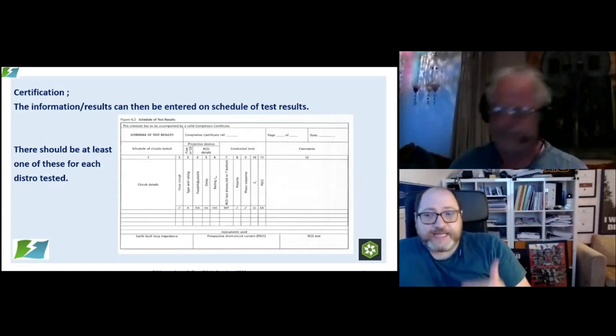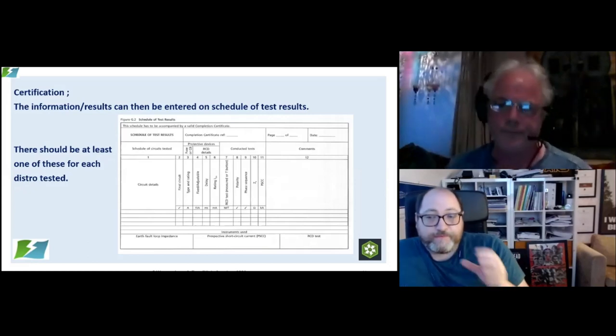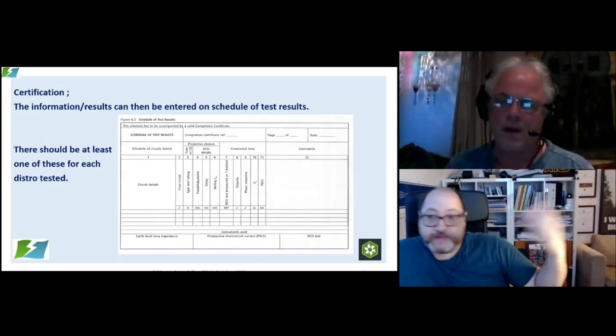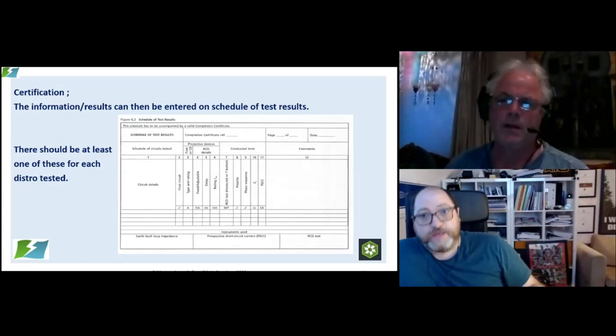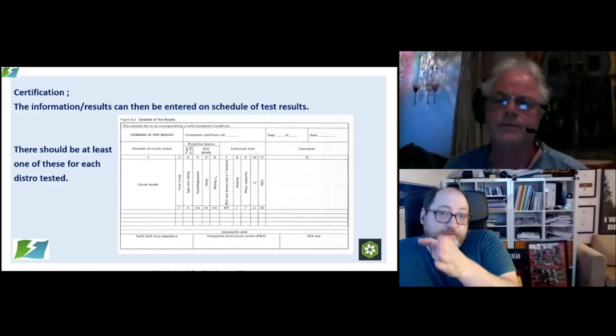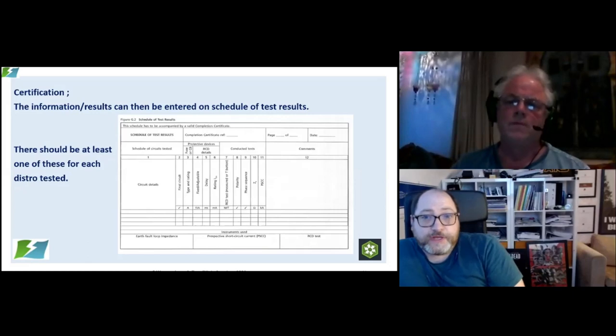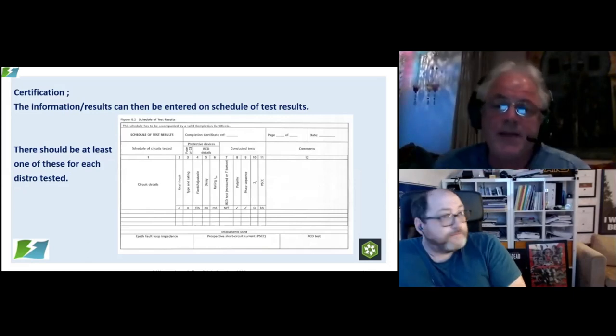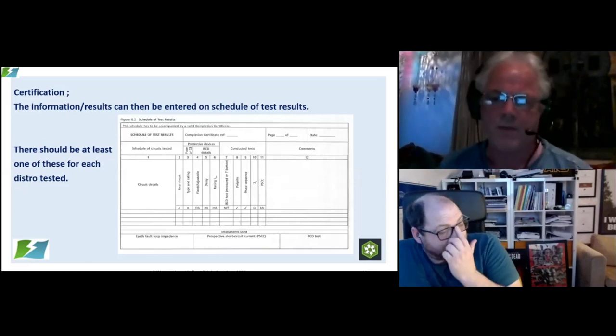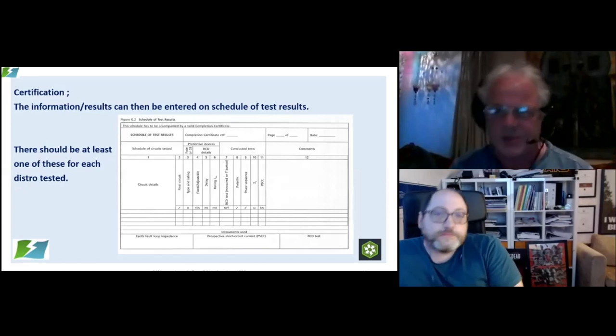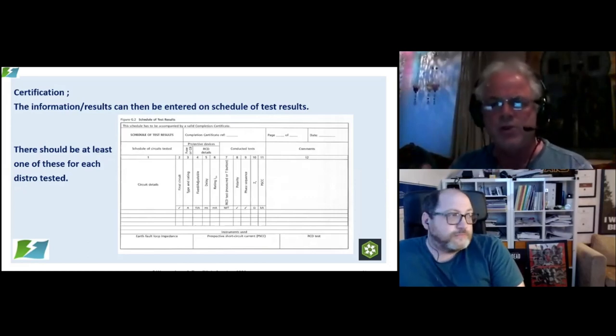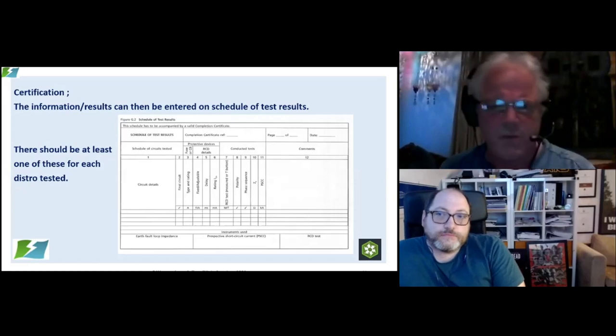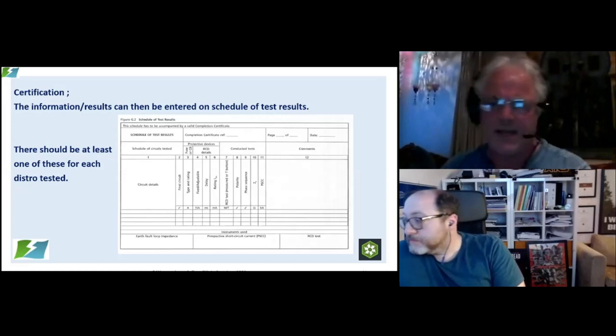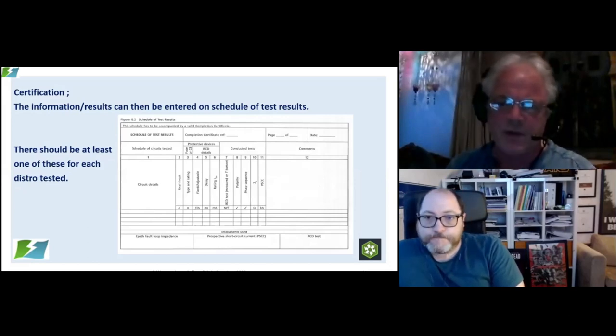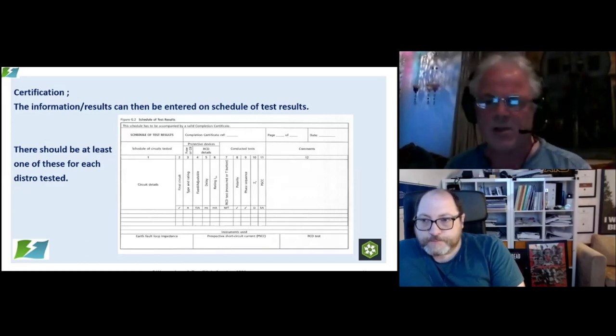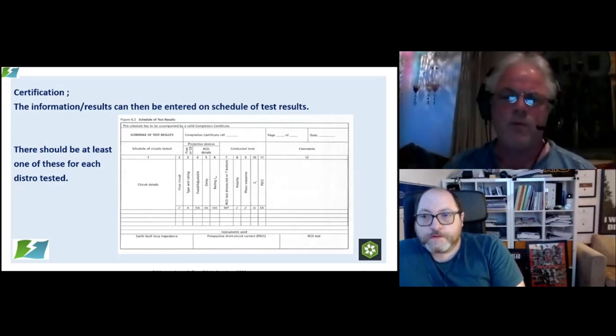What we need to do is connect it together and then work out what the value will be when we add the source of energy, which is the impedance, and the PSCC there, which is truly unique to 7909. Quite often, most of the time, the leads will come in standard sizes, standard lengths, so we should have a good idea of what the resistance should be. If we've got a 20-meter lead, which is a 32-amp using a 6-mil cable, we should know roughly what the resistance should be.